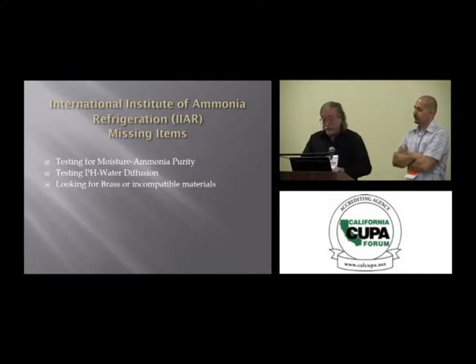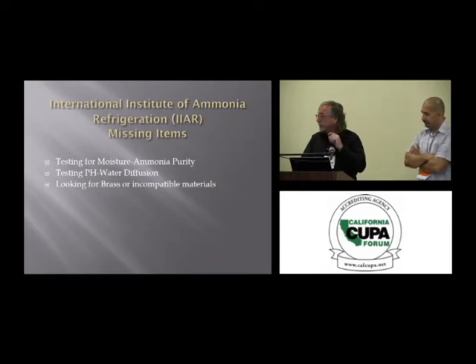Back here for the brass and incompatible materials, one thing we do carry in our back pocket when we do our mechanical integrity inspections, our walkthroughs, is a little magnet. And if we see anything that's suspect, we'll put the magnet on there. And if it doesn't stick, we have one of two things. We either have some kind of gold metal, or we've got stainless steel, which is compatible. So then we have to figure out which we have.